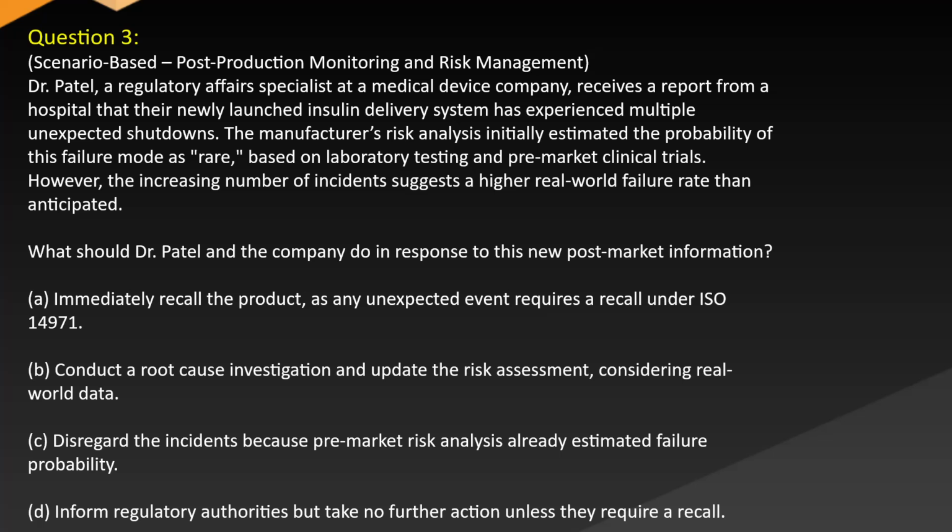What should Dr. Patel and the company do in response to this new post-market information? A. Immediately recall the product, as any unexpected event requires recall under ISO 14971. B. Conduct a root cause investigation and update the risk assessment considering real-world data. C. Disregard the incidents because the pre-market risk analysis already estimated the failure probability. D. Inform regulatory authorities but take no further action unless they require a recall.